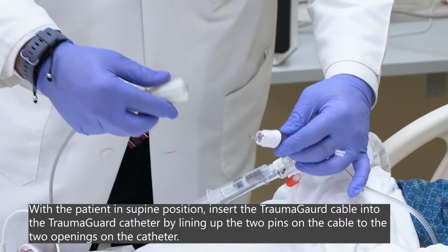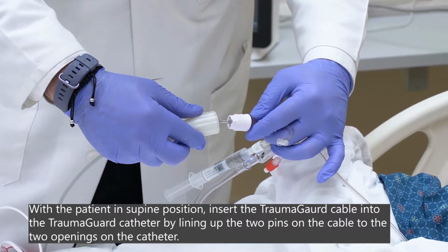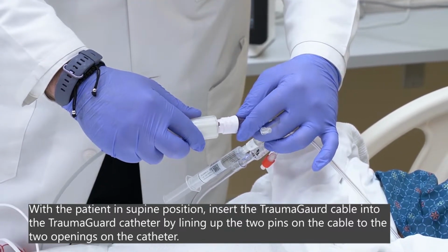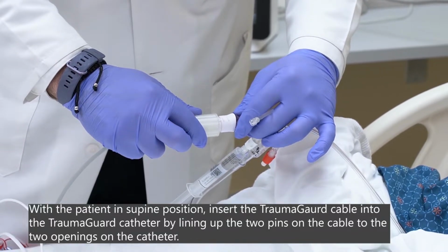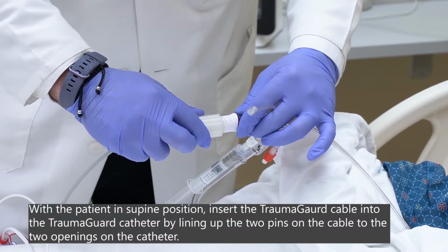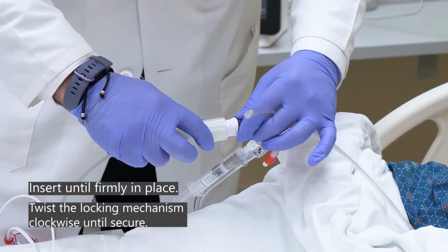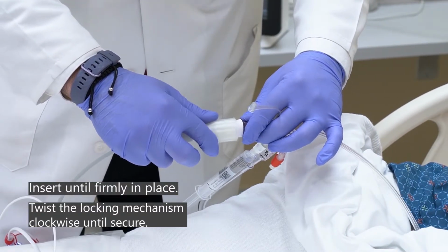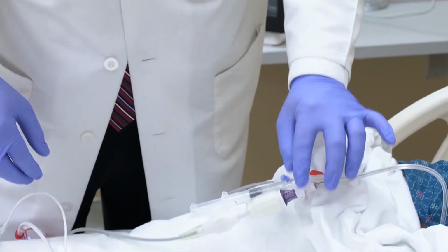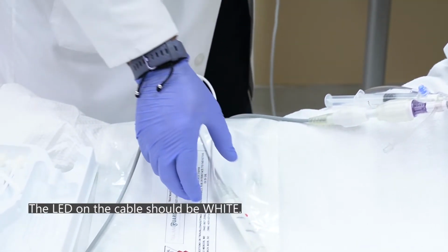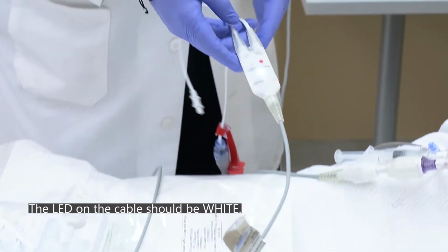With the patient in supine position, insert the TraumaGuard cable into the TraumaGuard catheter by lining up the 2 pins on the cable to the 2 openings on the catheter. Insert until firmly in place, twist the locking mechanism clockwise until secure. The LED on the cable should be white.